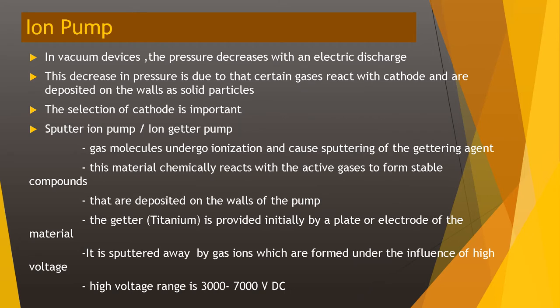In vacuum devices, the pressure decreases with an electric discharge. This decrease in pressure is due to certain gases reacting with the cathode and being deposited on the walls as solid particles — the selection of cathode is important. In the sputter ion pump, or getter ion pump, gas molecules undergo ionization and cause sputtering of the gettering agent. This material chemically reacts with active gases to form stable compounds deposited on the pump walls. The getter material used is titanium, provided initially by a plate or electrode, then sputtered away by gas ions formed under high voltage of 3000 to 7000 volts DC.